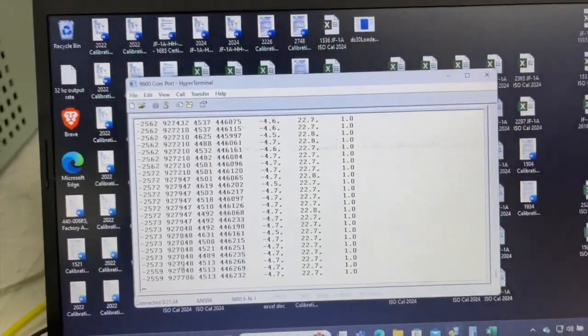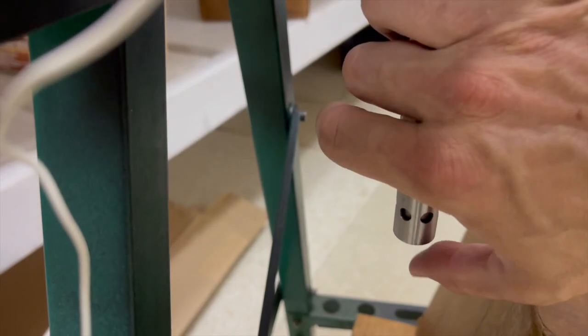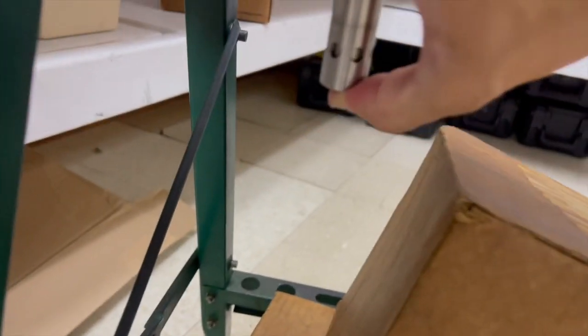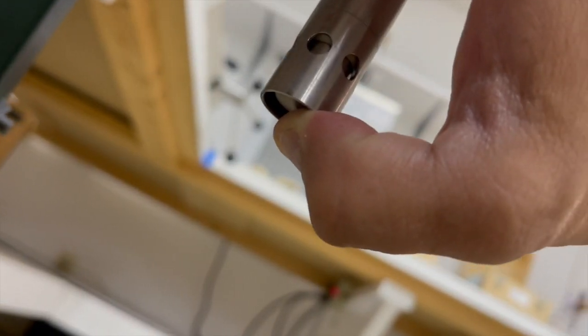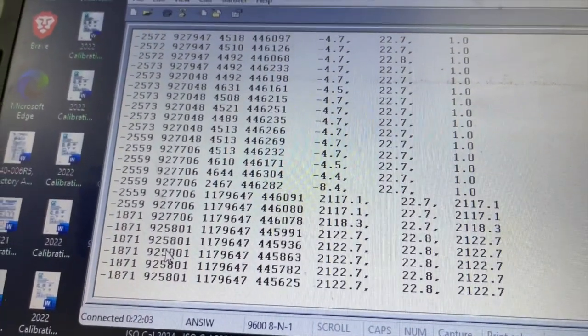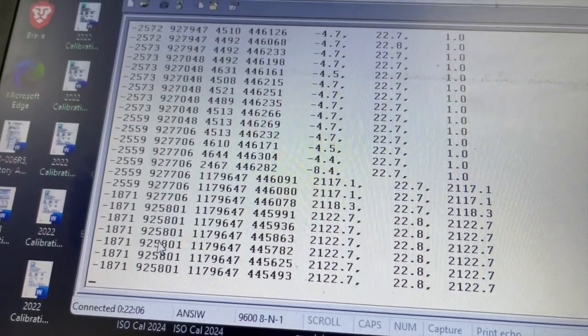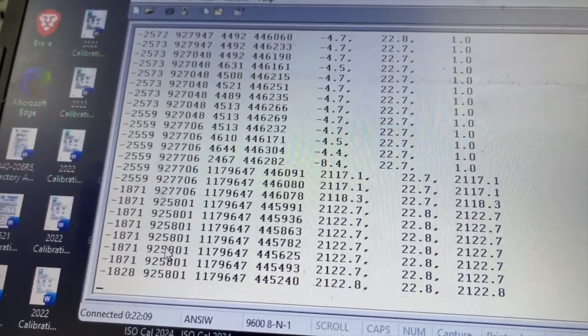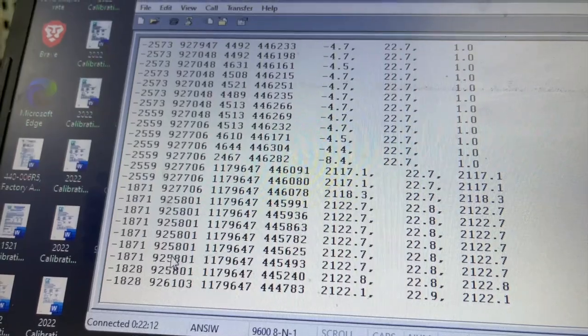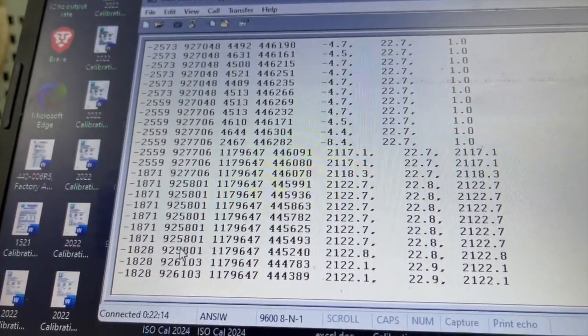The next thing that you're going to do to check the functionality is take your finger and put it across the two electrodes like so, so that the inner electrode is being touched by one part of your fingertip and it's crossing like so. You can see that. See how my finger's touching the inner electrode and the outer electrode? That shorts out the sensor. And you should get something like 1179647, which means conductivity is over scale, which is putting out 2122 for conductivity. And that lets you know that the conductivity is working.